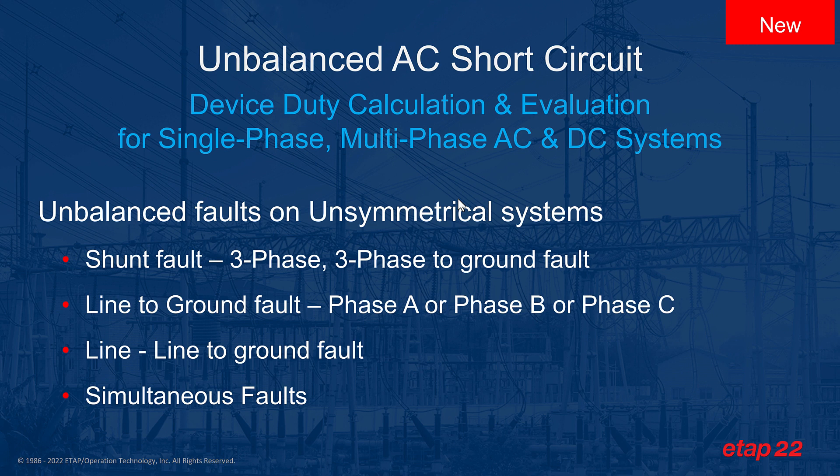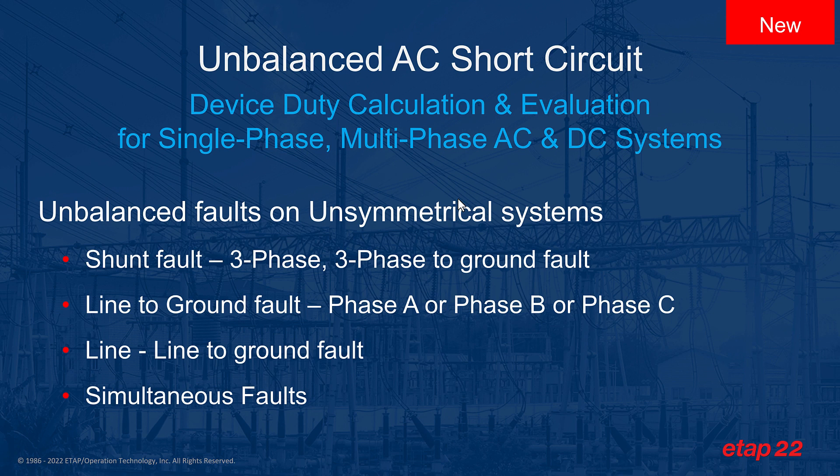With unbalanced short circuit, not only do you apply an unbalanced fault on an electrical system, but you're applying an unbalanced fault on an unsymmetrical system. These unbalanced faults can include shunt faults, line-to-ground faults, line-to-line-to-ground, as well as simultaneous faults.